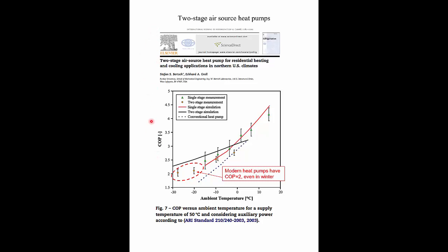There have been some really big engineering advances in heat pumps over the last couple of decades. There are modern two-stage air source heat pumps that really work well. This shows the COP of the heat pump versus ambient temperature — it's easier for heat pumps to pump heat into your home on a warm day than on a really cold day. But even on the worst cold days, like minus 20 or minus 30 in Toronto, a good modern two-stage air source heat pump can have a COP of two. Whereas on a nice fall day at maybe 10 degrees, you're getting something like four units of heating for every unit of electricity. This is taken from a research paper — modern heat pumps are pretty amazing devices.